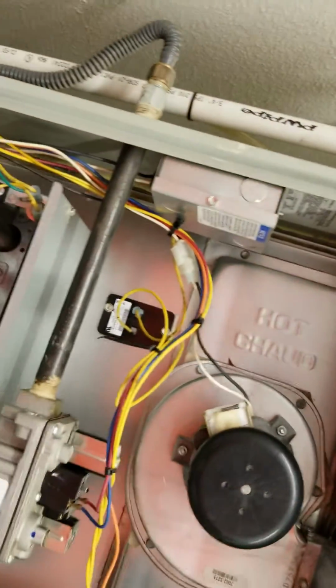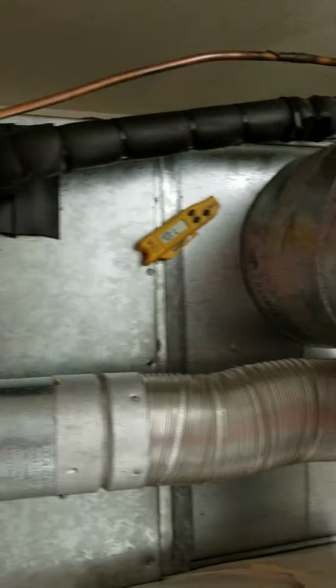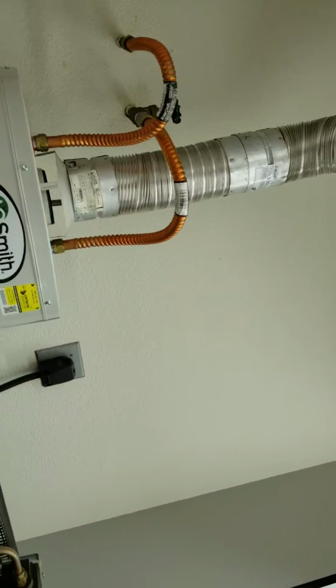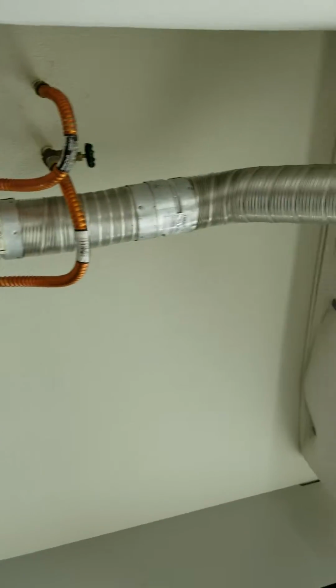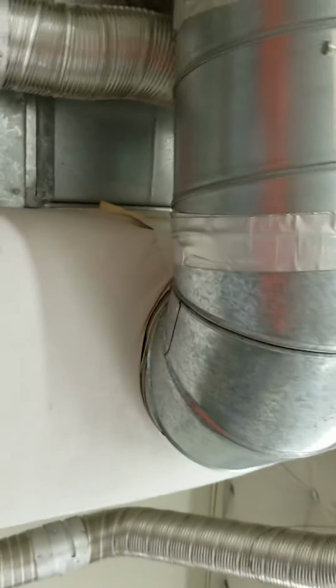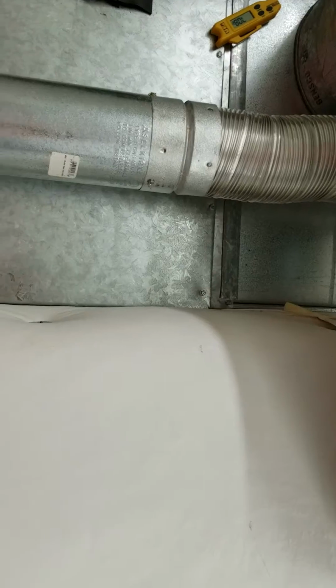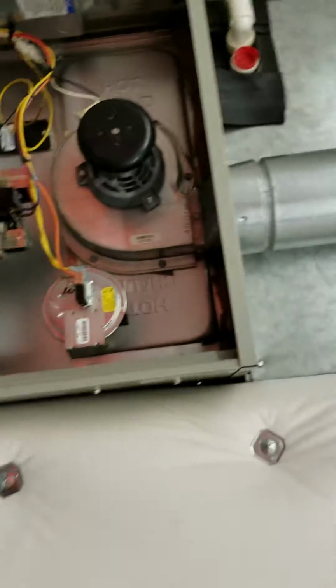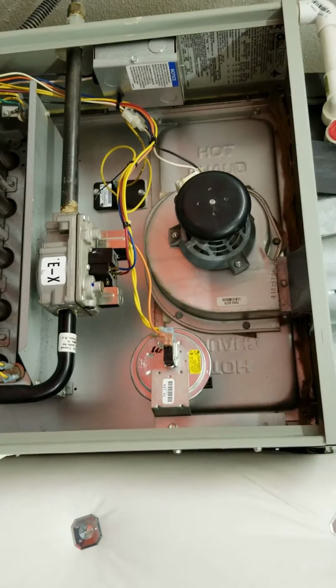Inspect our cabinet for drains, broken piping, anything like that. In this case, it has air conditioning on it, but the drain piping is all secure, and so on. Again, inspect our flue all the way down. In this case, the water heater is right next to it, so go ahead and take a look at the flue for that too. Make sure that no flue is loose or anything, because then that pumps exhaust into the building. So now we're waiting for our furnace safety delay.